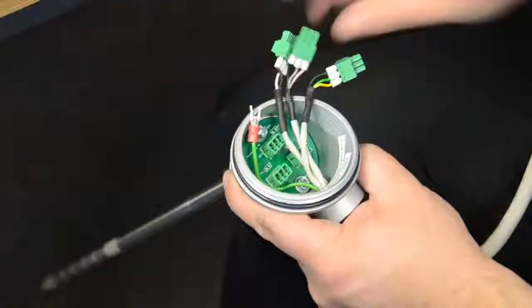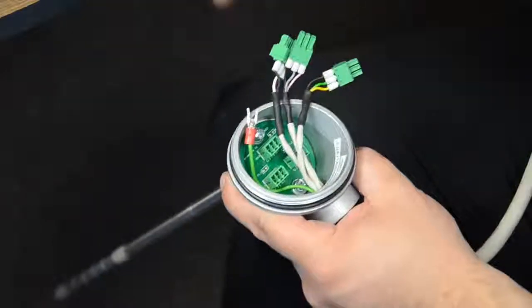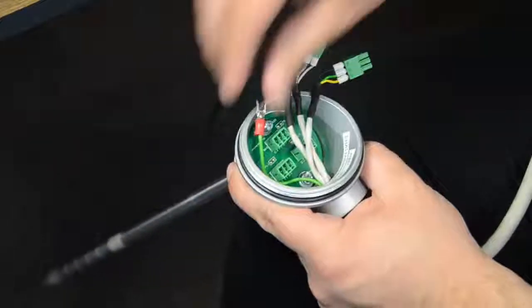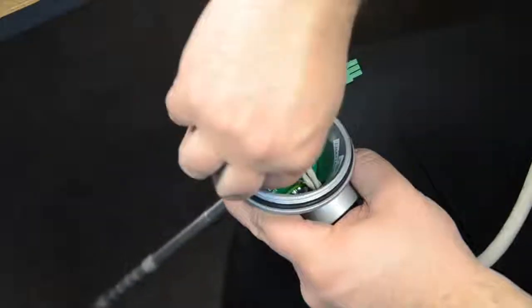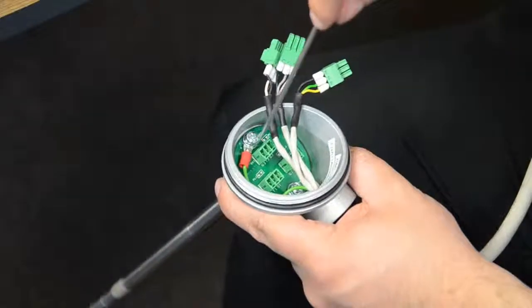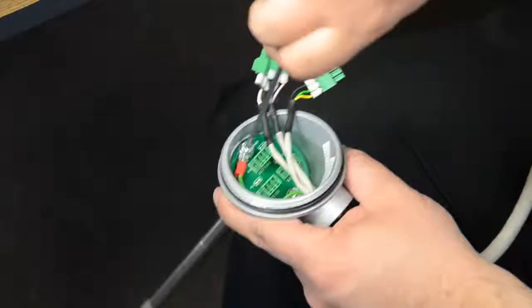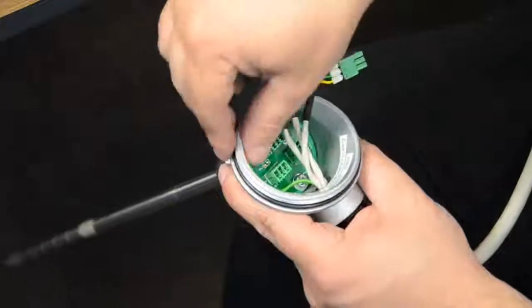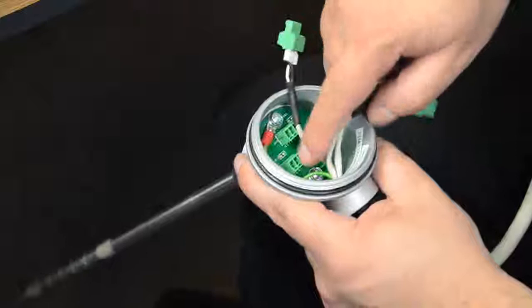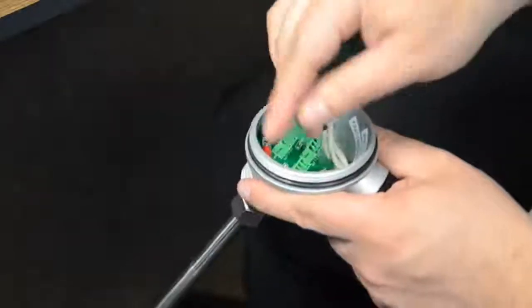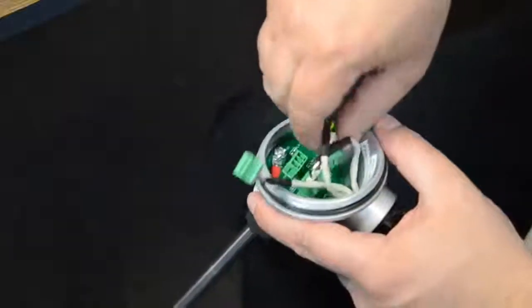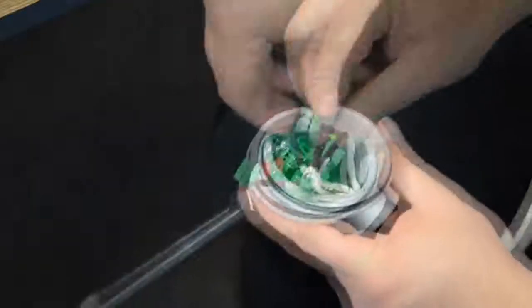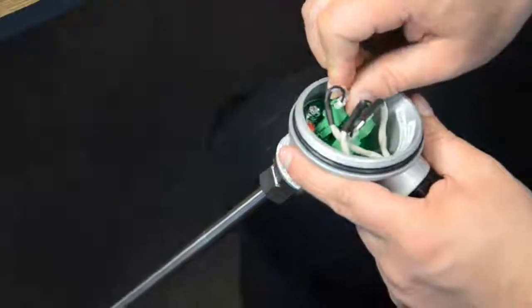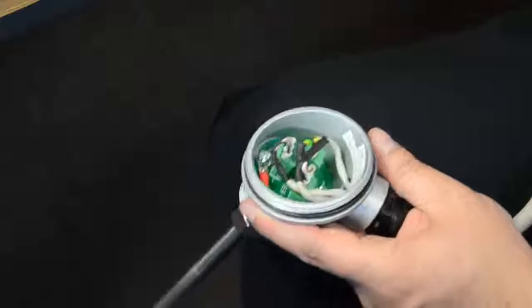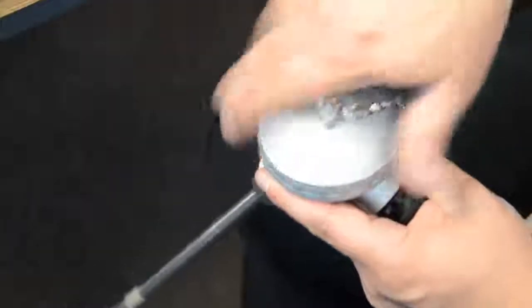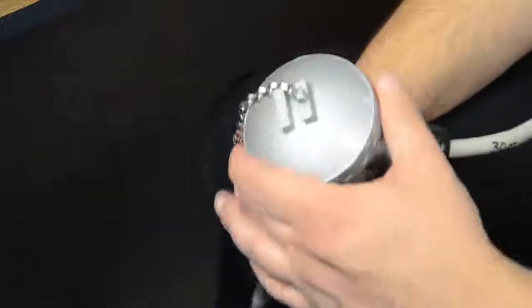So once we've wired into our terminal blocks, we're going to want to insert them back into the probe. It might be a good idea before that, if you're using a metal tank to earth your probe, connect your earth underneath the screw in the head of the probe. Like so. Okay, so sense point 1 is our brown, black and white, and that goes into SK1 down the bottom here. Sense point 2, which is our yellow cable, goes into the bottom right, and sense point 3 goes in at the top. Once this is wired up, we can replace the head. And we've finished wiring up the SureSense Plus.